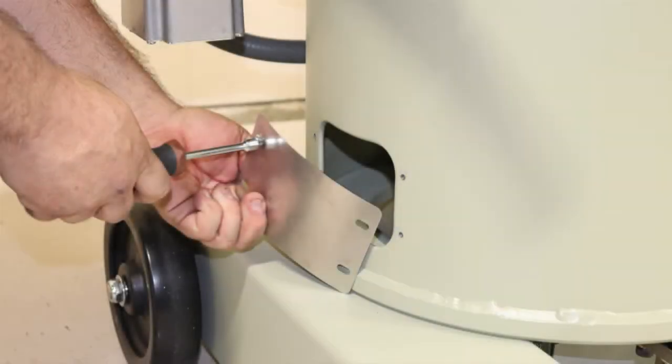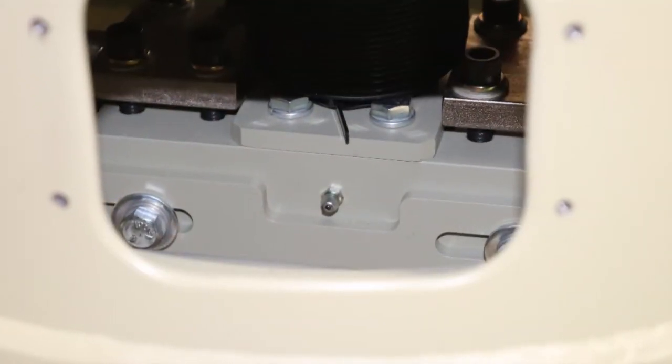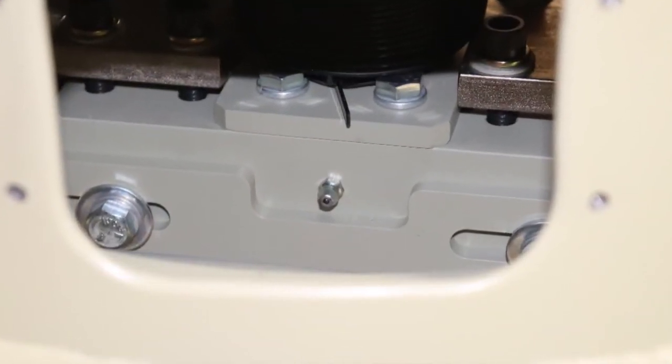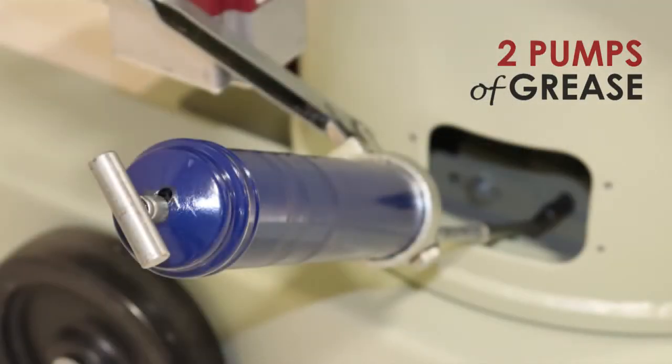Next, you will remove the ball screw bearing cover on the lower left side of the machine using the 5/16 nut driver. Due to the location of the ball screw bearing, it is necessary to have a 45 degree adapter on the end of your grease gun. Grease the fitting with two pumps, then replace the cover.